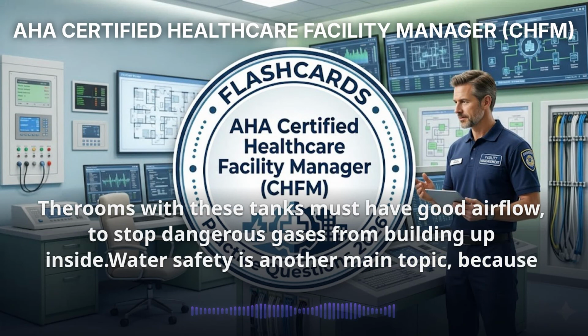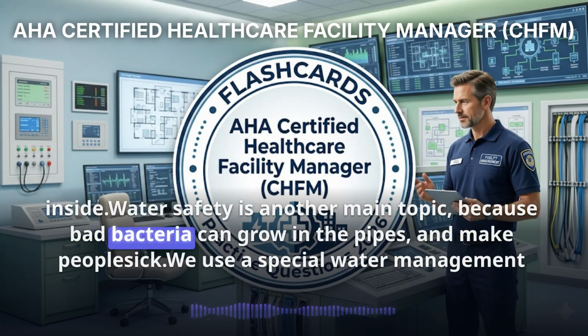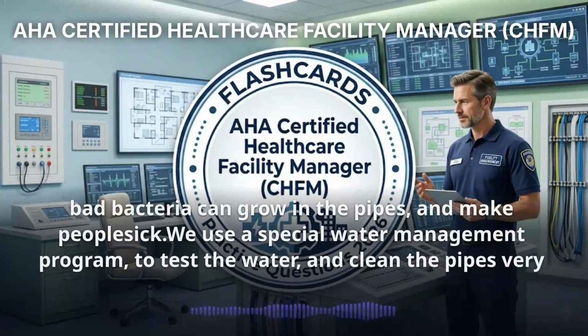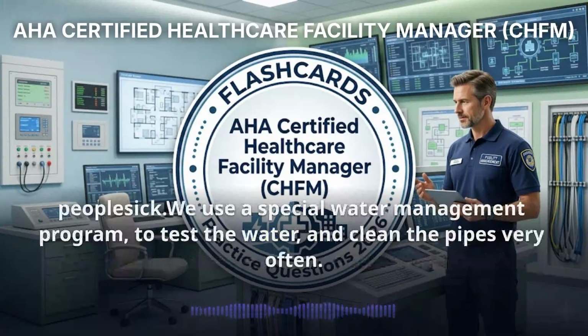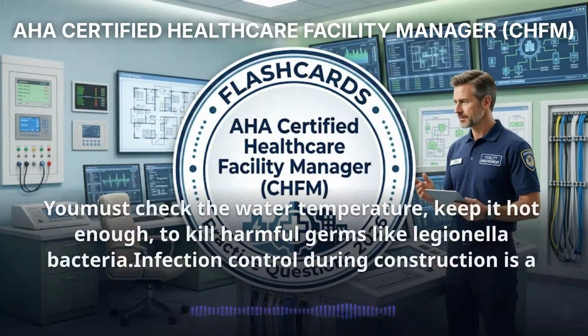Water safety is another main topic, because bad bacteria can grow in the pipes and make people sick. We use a special water management program to test the water and clean the pipes very often. You must check the water temperature, keep it hot enough to kill harmful germs like Legionella bacteria.